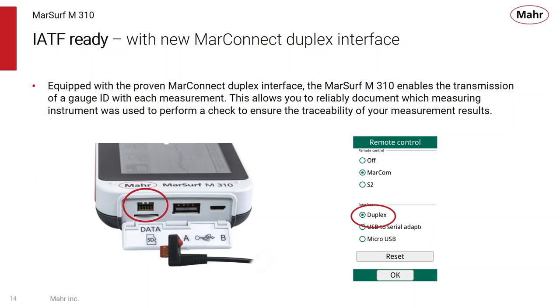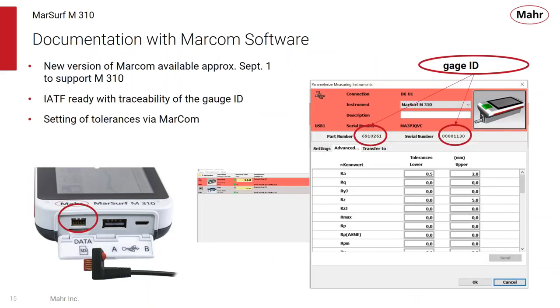And this is done with the MarConnect duplex cable. Because it uses this cable, we can identify the gauge ID number with the product. So now you can document not only the measured values, but also the instrument that was used to perform the check, to ensure traceability of your measurement results. You can do this documentation through the free Marcom software. Go to Mahr.com and you'll be able to locate the software. Starting September 1st, it's going to support the M310.